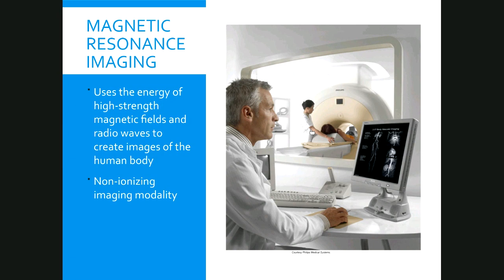When we used to walk by the MRI suite, anything that you had that was metal would pull towards that. Now they usually have a door that is kept closed so that people that are passing by are not affected. But I can also tell you that there's different zones now with MRI where if you're not qualified to a certain level, you're not even allowed back near the magnet. Typically, the technologists are allowed back there. They have to have a certain level of clearance.